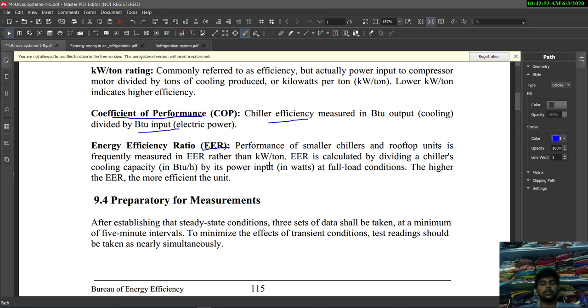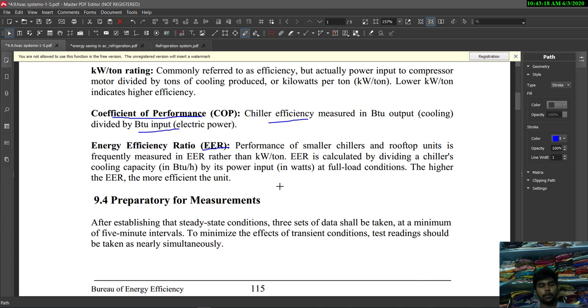Next is EER — energy efficiency ratio. The performance of smaller chillers and rooftop units is frequently measured in EER rather than kilowatt per ton. It is calculated by dividing the chiller's cooling capacity in BTU per hour by its power input at full load condition. The higher the EER, the more efficient the unit.